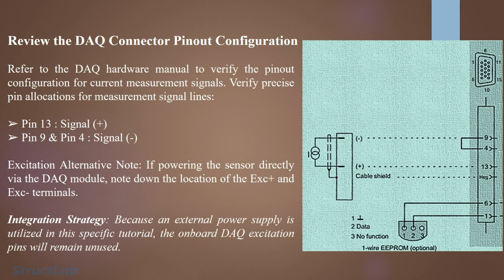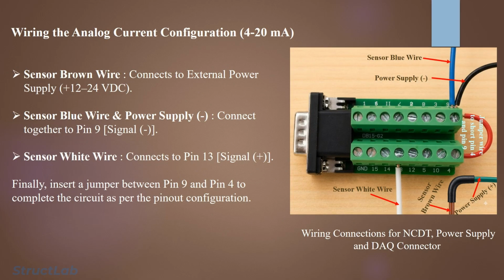Step 3. Review the DAQ connector pinout configuration. Refer to your DAQ hardware manual to verify the correct pin locations for an analog current input. Examining the diagram, our primary objective is to locate the measurement signal lines. Pin 13 maps to signal plus, while pins 9 and 4 map to signal minus. As an alternative, if you choose to power the sensor directly from the DAQ module, you would use pin 12 for excitation plus and pin 11 for excitation minus. However, because our integration strategy uses a dedicated external power supply for this tutorial, these onboard DAQ excitation pins will remain unused.